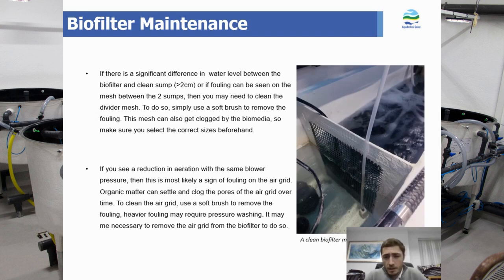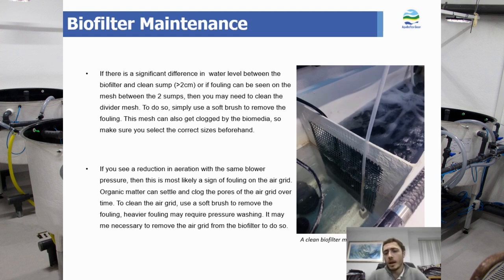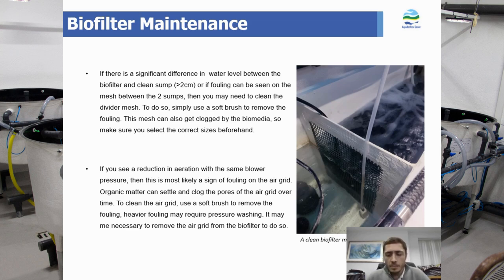You can see in this picture a clean sump on the left of the biofilter — this is quite a small and new biofilter. Some of the issues you might find is fouling on the mesh, which means a reduced flow from the dirty to the clean sump. If you see a difference between water levels of about two centimeters, you might want to take a light brush and just clear away some of this fouling. Additionally, if you see a reduction in the aeration even though the blower is working at the same capacity, then you might have fouling on the air grid within the biofilter. So you would want to remove the grid and just clear away any fouling, and then place it back evenly — which is quite important so that it doesn't become lopsided — and then just restart the system.